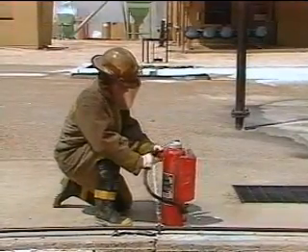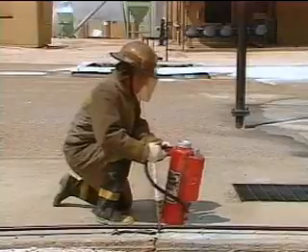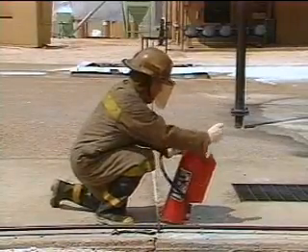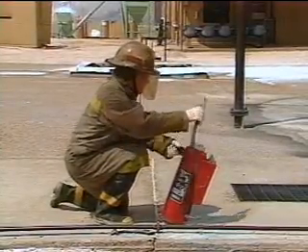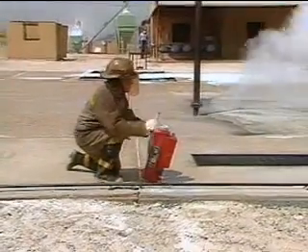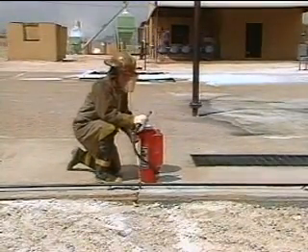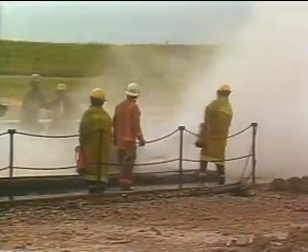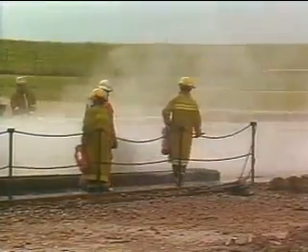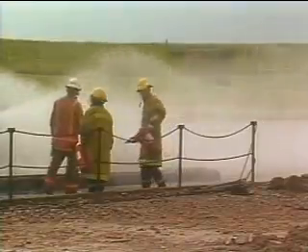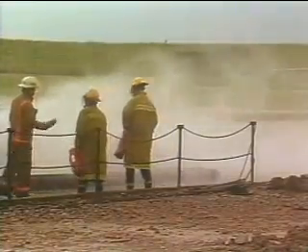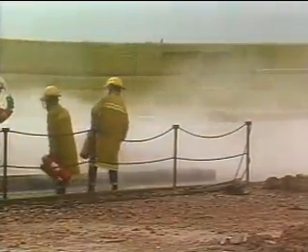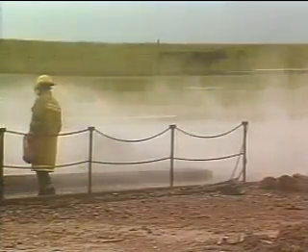And always hold the hose tightly when charging. Don't lean over the unit when charging it, since the cap might blow off, causing injury. Regardless of the charging requirement, an extinguisher should never be activated unless you're going to fight a fire. Once the seal is broken, the extinguisher must be reserviced and returned to a ready condition.